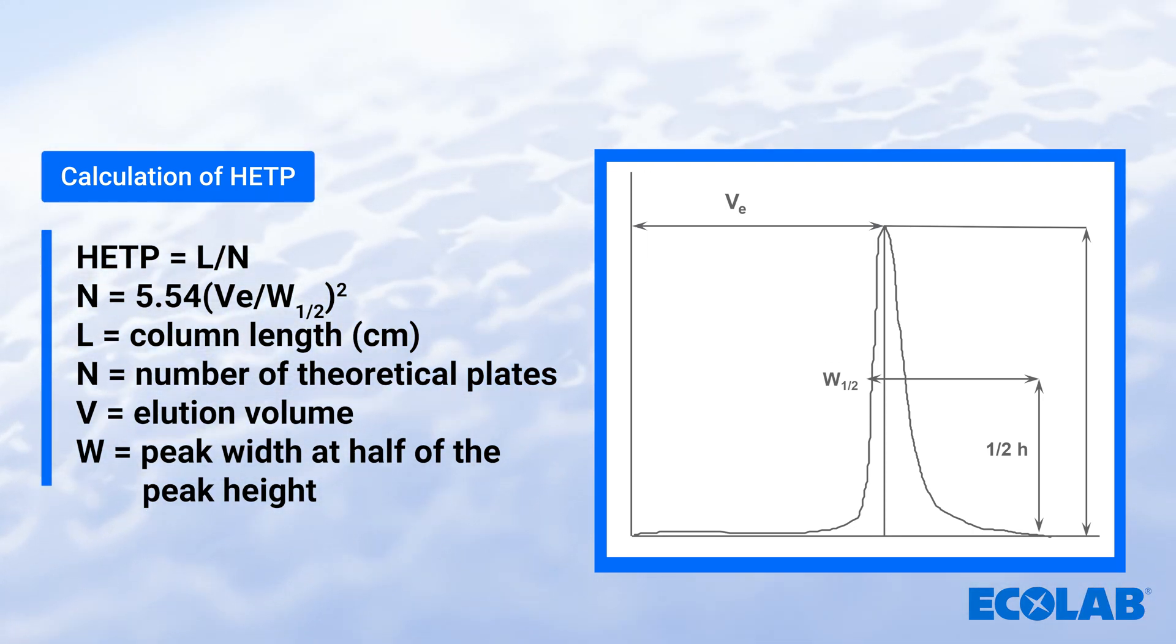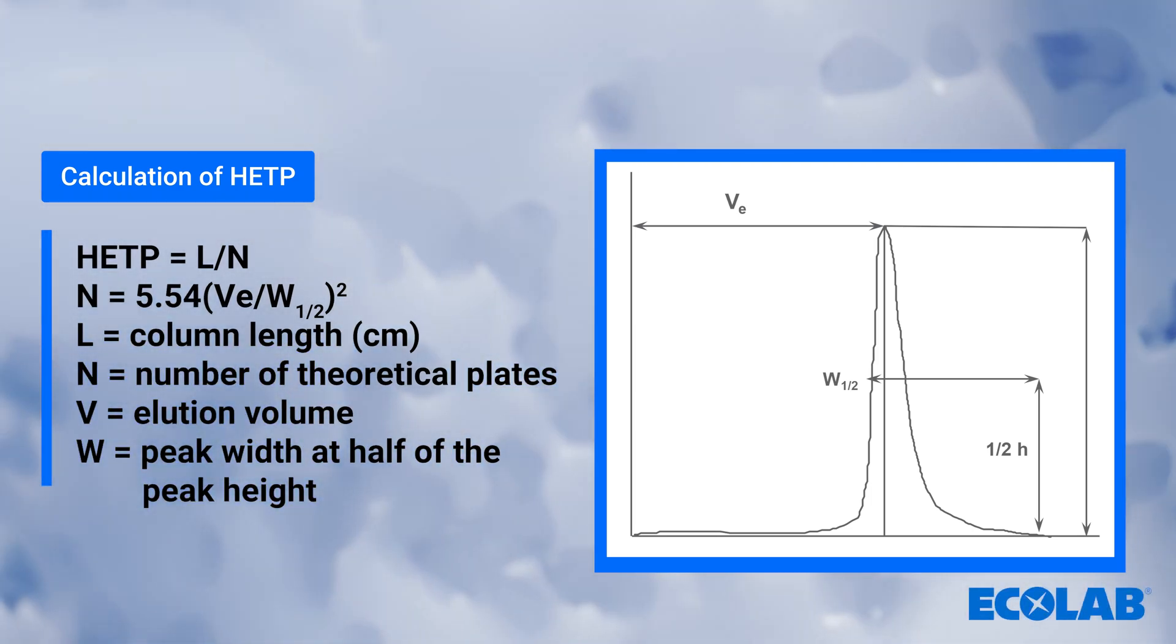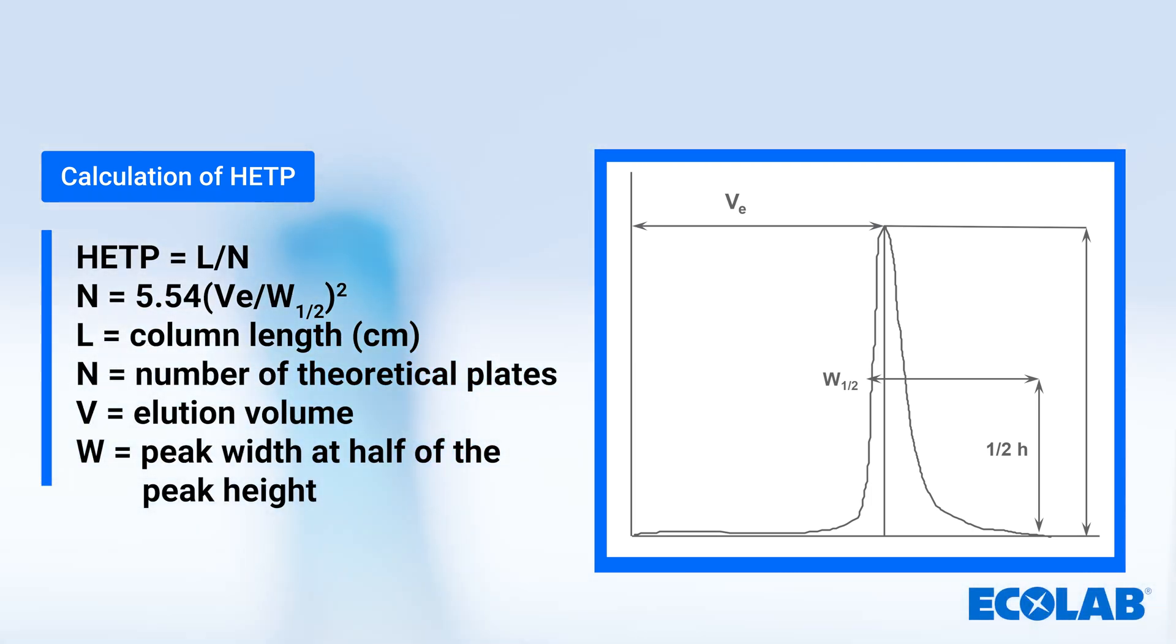The lower the HETP, the better the resolution and the more efficient the separation. Efficiency is optimized when N is maximized and the HETP is minimized. HETP will vary with the flow rate, so it is important to have an SOP with set values for testing the column.